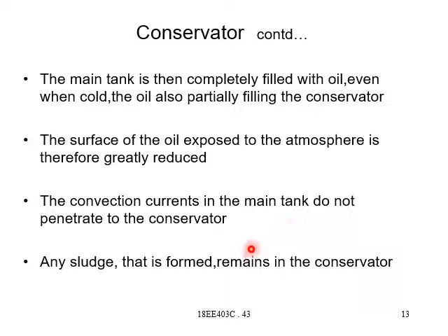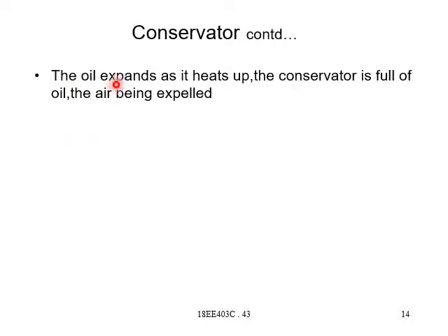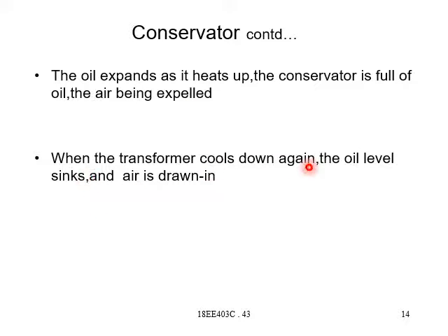Okay, moving on to the next slide. In the continuation of conservator, the oil expands as it heats up. So the conservator is full of oil, the air being expelled. When the transformer cools down again, the oil level sinks and air is drawn in. This action is known as breathing. So you can know that breathe in and breathe out, we human beings do it actually, called breathing.